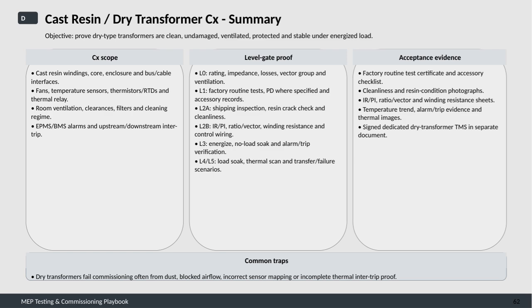For acceptance, it's essential to provide evidence such as factory test certificates, accessory checklists, photos of cleanliness and resin condition, test sheets for insulation resistance and winding resistance, temperature trend data, alarm and trip logs, as well as thermal images. All this documentation is compiled into a dedicated dry transformer test management system document.